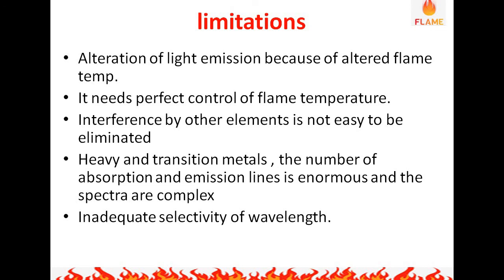The limitations of flame photometry include: alteration of light emission due to altered flame temperature, requiring perfect control of flame temperature. There is interference by other elements, which is not easy to eliminate. For heavy and transition metals, the number of absorption and emission lines is enormous and the spectra are complex, making determination impossible. There is also inadequate selectivity of wavelength in flame photometry.